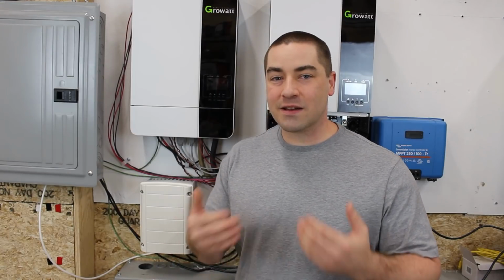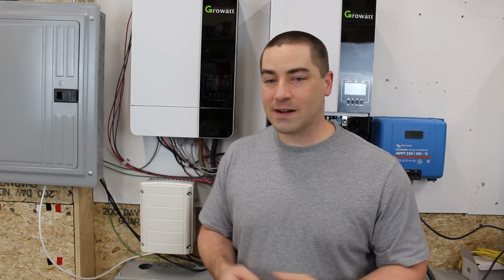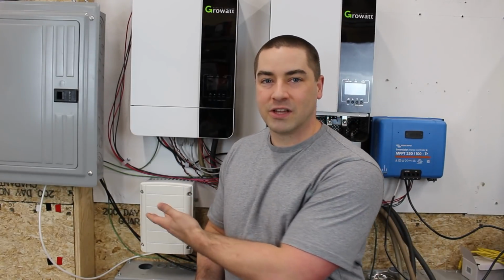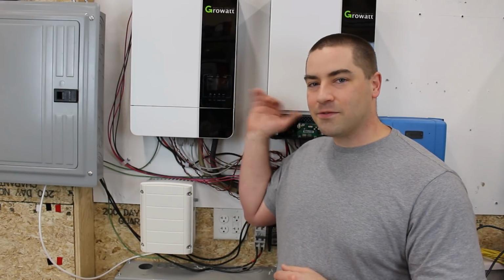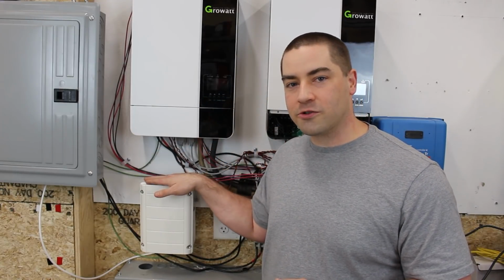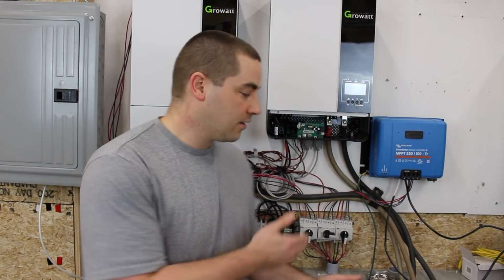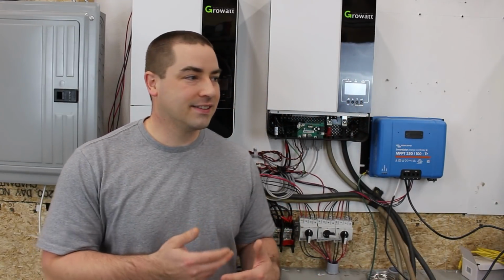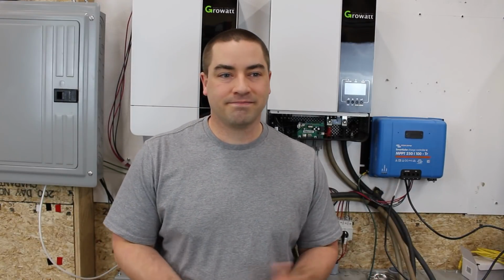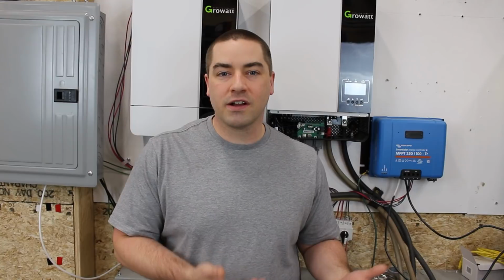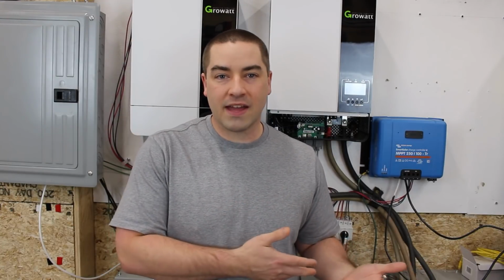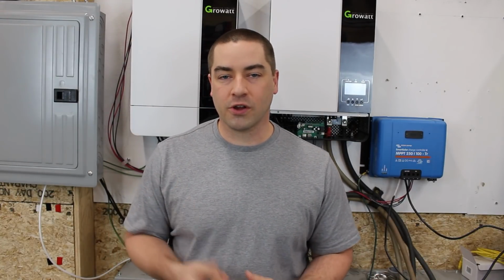Now what that means is, for me personally, in my setup, I'm not loading down this auto transformer. I mean, it hardly sees any work. Since I have 2 inverters, if I had 2 auto transformers going to the terminal block, there's really, at that point, I would say it's unrealistic that me or anybody who visits my house could overload them.